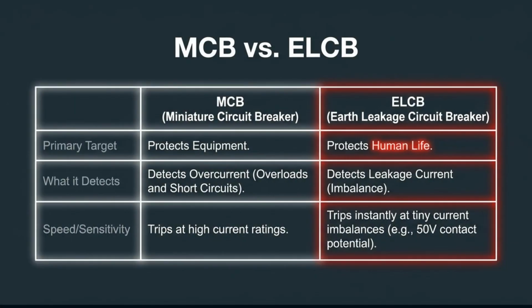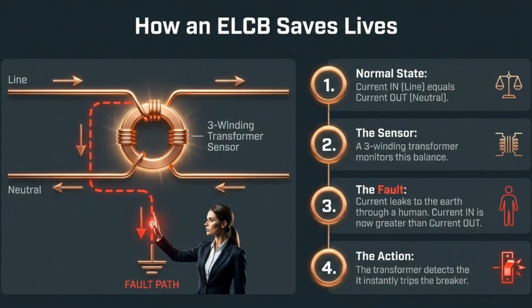Unlike MCBs, which protect equipment from overcurrents, earth leakage circuit breakers, or ELCBs, protect human life. ELCBs detect tiny leakage current imbalances and trip instantly. An ELCB works by monitoring the current balance between the line and neutral with a 3-winding transformer sensor. If current leaks, indicating a fault, the imbalance is detected and the breaker instantly trips.